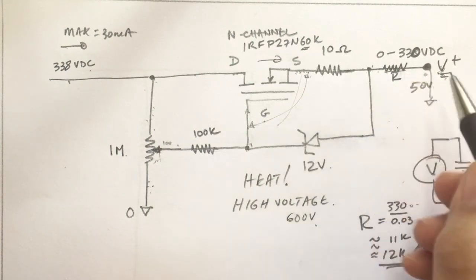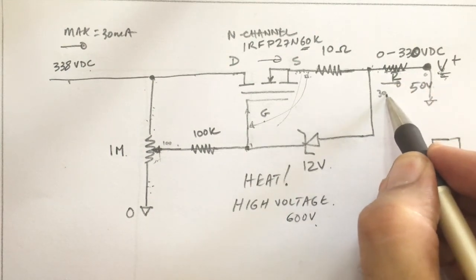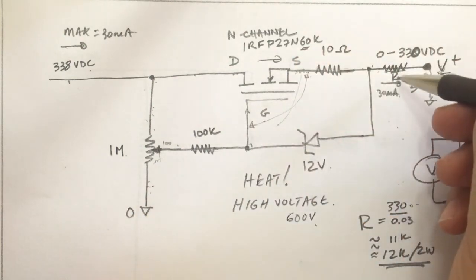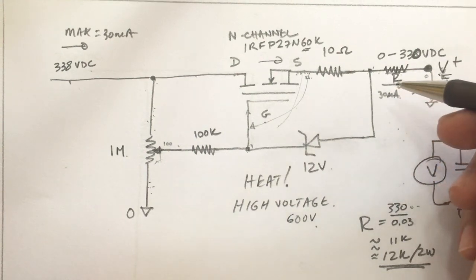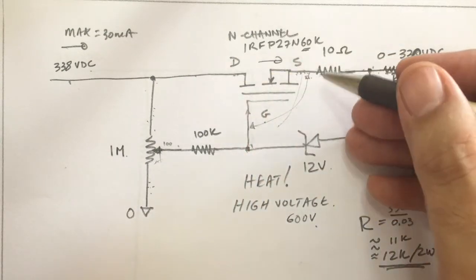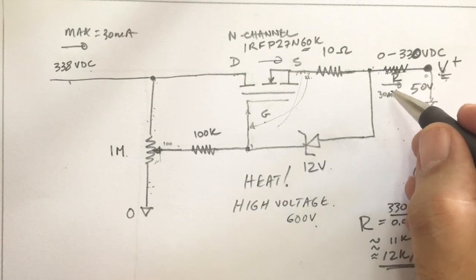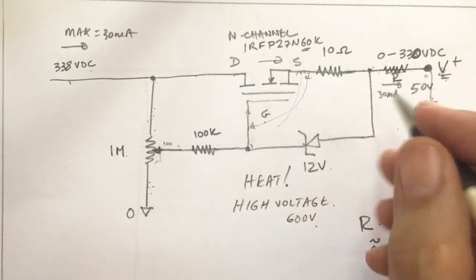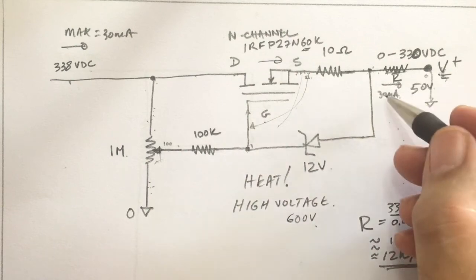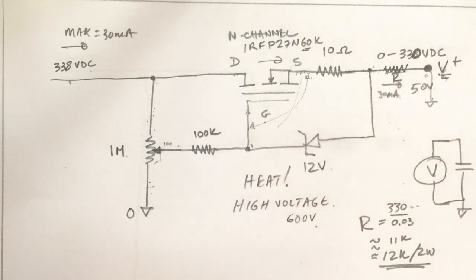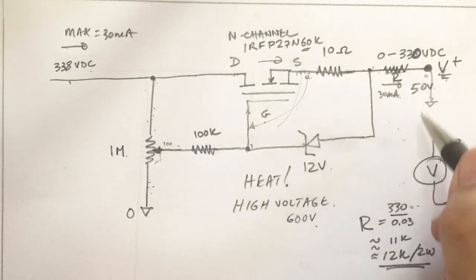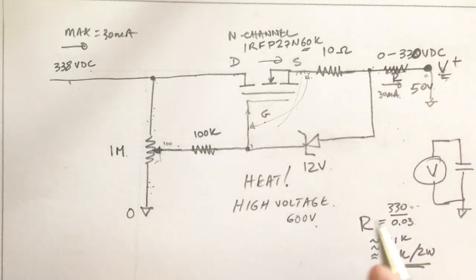So if I do short it out, I end up with a maximum of 30 milliamps through here, and I've protected the system somewhat. Obviously, if this stays on there for very long, I'm going to have a problem because this will heat up and the transformer will be supplying its maximum voltage and current. That's not good, but at least I'll see it on my meters since I'm there on the spot. I can then reduce the voltage immediately or switch off the system because I know I have a short to ground, or an incredibly high leakage on the capacitor, which is practically the same thing. So our 12K resistor reduces that.